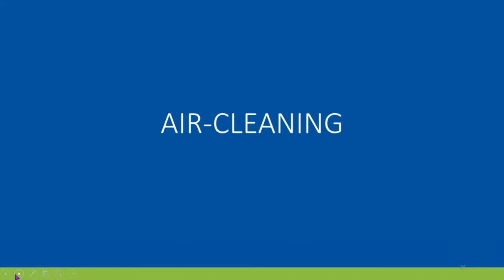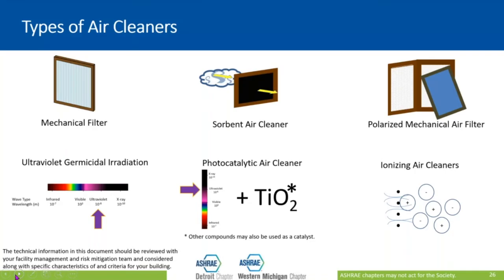When we look at air cleaning, there are a number of types of filters. What we're doing with the filter is trying to approximate clean outdoor air, right? The EPA in the States, the Environmental Protection Agency, has set standards for 6 common contaminants in outdoor air. And part of the design process for the HVAC system entails confirming that the outdoor air we're going to be using, which is the basis for the indoor air, is sufficiently clean. Depending on what the contaminant is, we may have to document some sort of strategy for making that air clean, or for ozone or particulate matter, we have to apply certain types of filters.